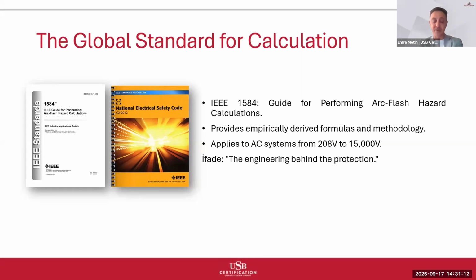The IEEE standard represents the engineering behind the protection. When we specify PPE requirements based on arc flash analysis, we are not making conservative guesses. We are applying validated engineering methods. The standard is regularly updated as new research becomes available. The most recent revision in 2018 incorporated new understanding of arc behavior. The former one is the 2002, particularly for lower voltage systems and different enclosure types. This is why a qualified arc flash analysis requires both specialized software and engineering expertise. It's not just data entry. It requires understanding the underlying physics and the limitations of calculation methods.